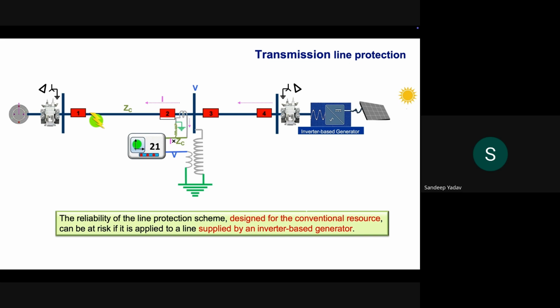So the reliability of the line protection scheme, because they were designed for conventional resources, could be at risk when there is a transmission line which is solely supplied by an inverter-based resource. So for this fault near terminal 1, because the terminals 4, 3, and 2 will see the fault current fed by the inverter-based resource, the impedance protection 21 at terminal 2 will have a difficult time in terms of detecting the fault and clearing the fault. We'll see in the upcoming slides why.